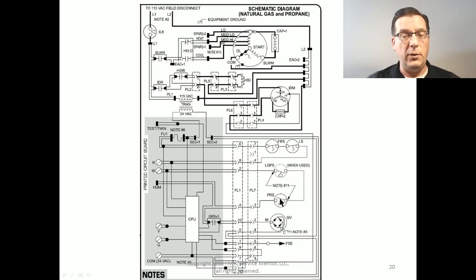And here we have another voltage send and return binary digital input. It's receiving 24 volts on W, and that 24 volts now leaves the board through the Molex plug, passes through the pressure switch. Well, it just lands on the pressure switch and it waits. Once the draft inducer is running, then the pressure switch will close and allow that voltage to come back to the control board, and this is our voltage return. Then that voltage now becomes another pass-through while it sits and waits at the incoming side of the gas valve relay. Once the pressure switch is closed, the control board says, okay, time to go to the next step.